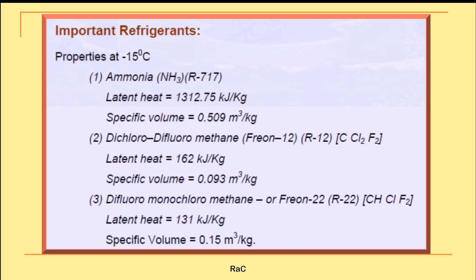Common refrigerants in use include R717 (Ammonia), R12 (Freon 12, Dichlorodifluoromethane), and R22 (Freon 22), which have been used since refrigeration was invented. Nowadays these have been replaced by R134a and R410A as zero-ODP refrigerants. Newer refrigerants are under research to eliminate global warming potential and ozone depletion potential by removing CFCs and HCFCs containing fluorine and chlorine.